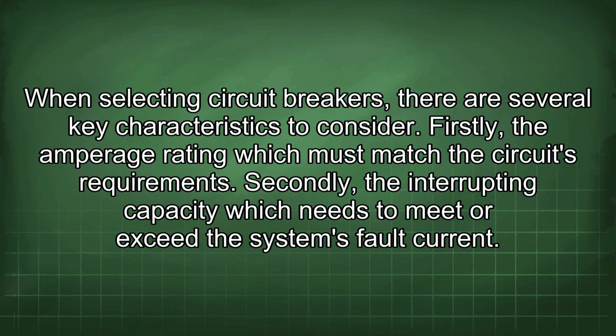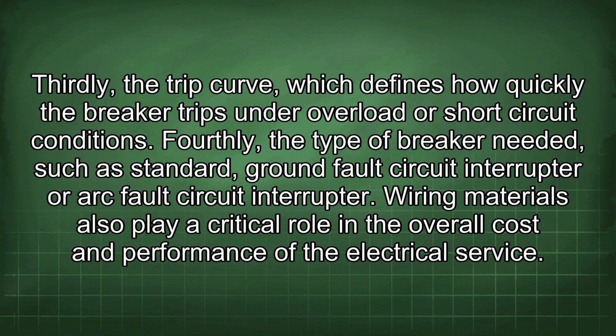When selecting circuit breakers, there are several key characteristics to consider. Firstly, the amperage rating, which must match the circuit's requirements. Secondly, the interrupting capacity, which needs to meet or exceed the system's fault current. Thirdly, the trip curve, which defines how quickly the breaker trips under overload or short circuit conditions. Fourthly, the type of breaker needed, such as standard, ground fault circuit interrupter, or arc fault circuit interrupter.